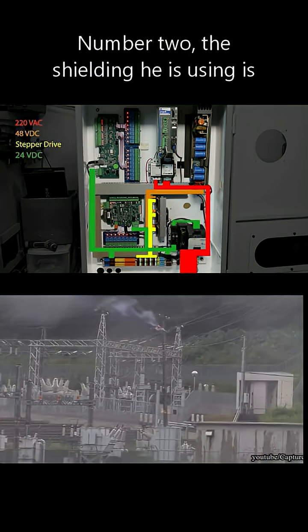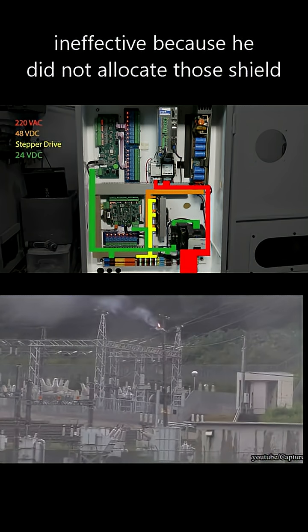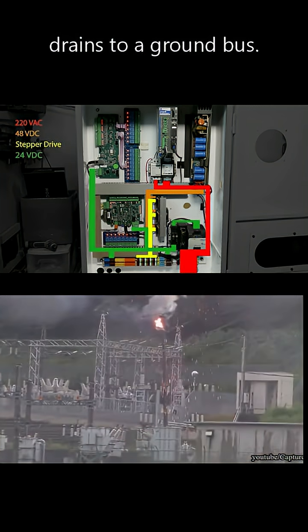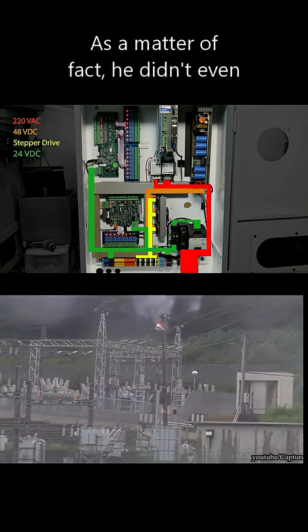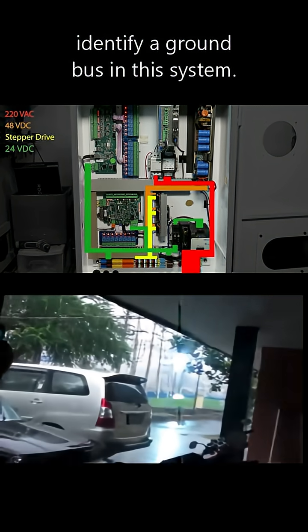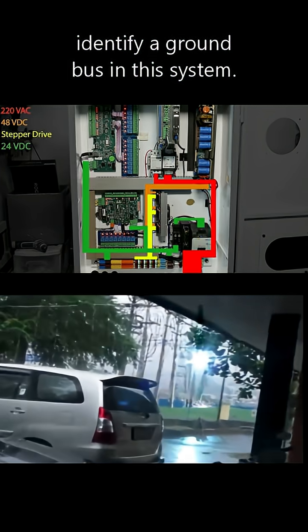the shielding he is using is ineffective because he did not allocate those shield drains to a ground bus. As a matter of fact, he didn't even identify a ground bus in this system.